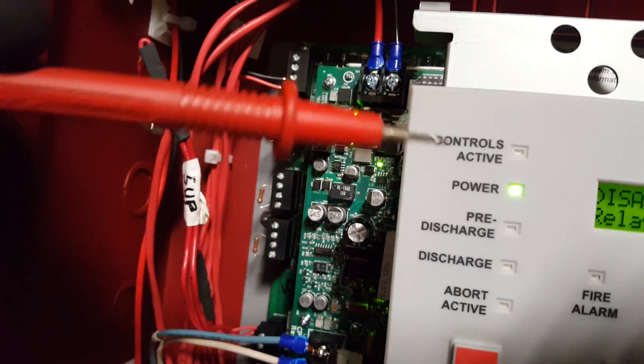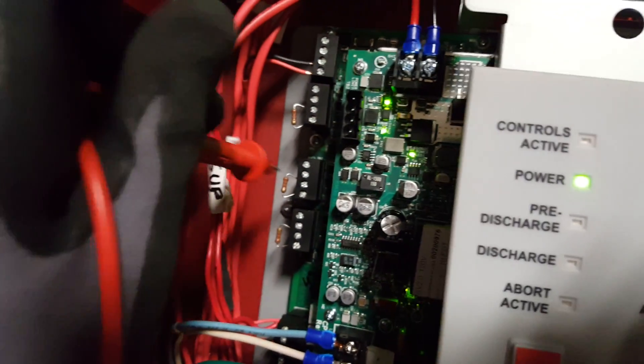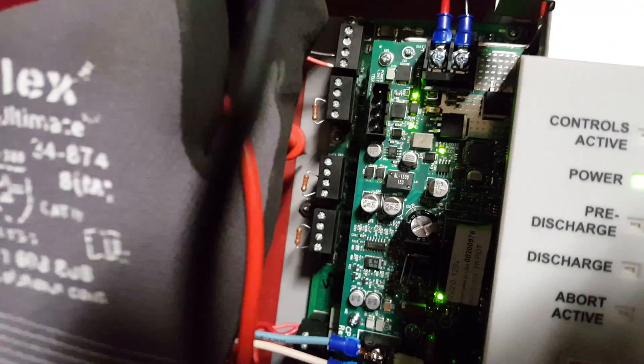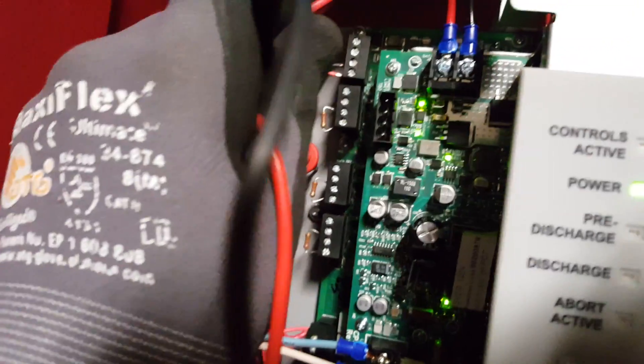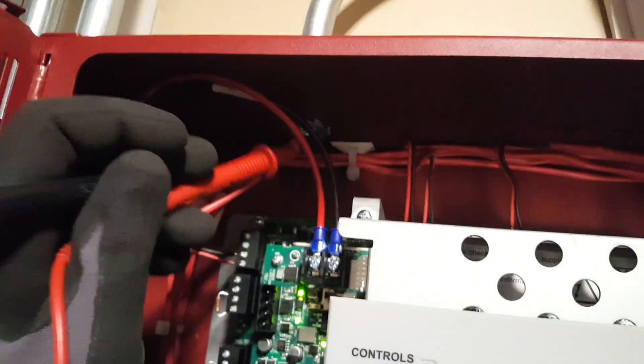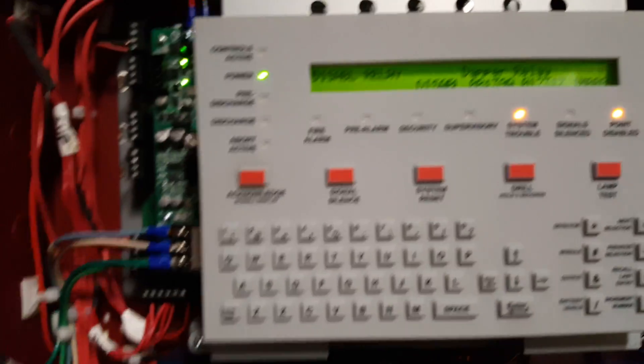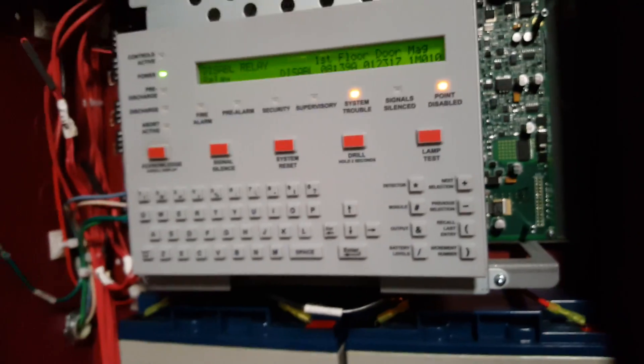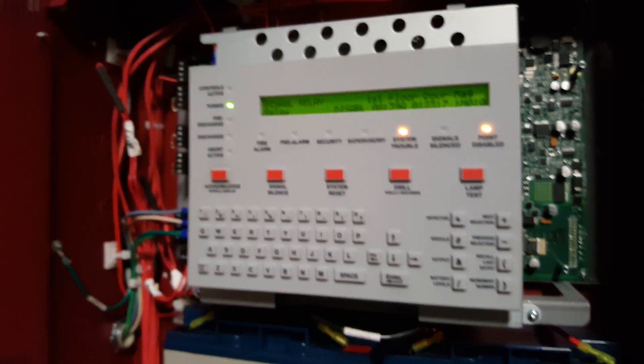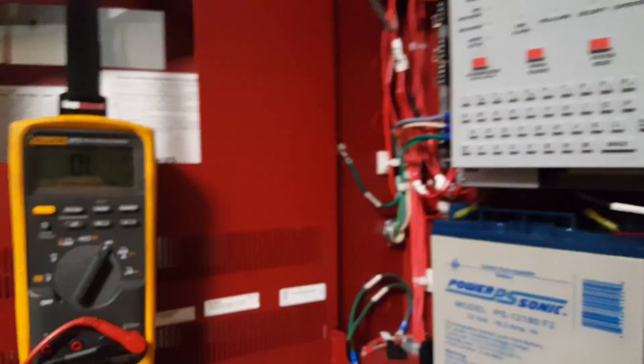And again, you want to have your other lead from your meter go into a ground source, so this backboard here, sometimes the pipe coming in feeding the wires, or a screw in the back that you could use as your ground source. And that's how you test for a ground fault at the fire panel using your multimeter.